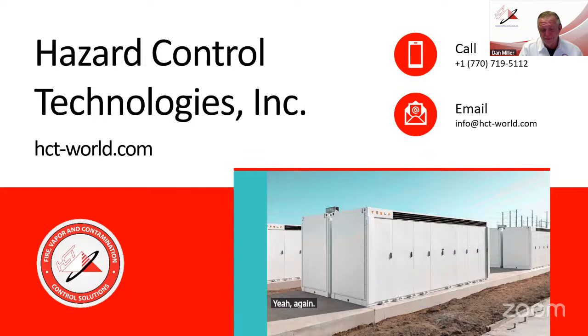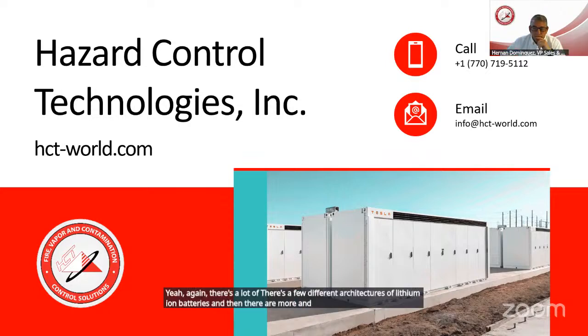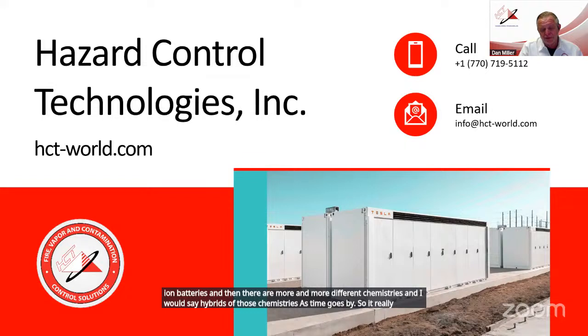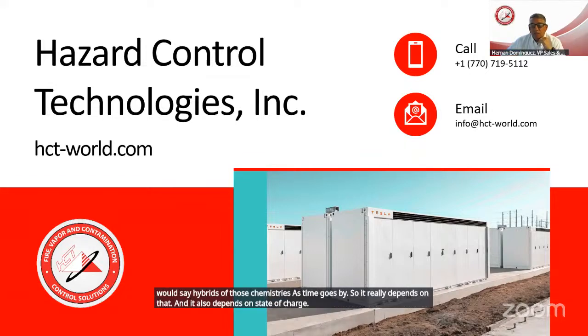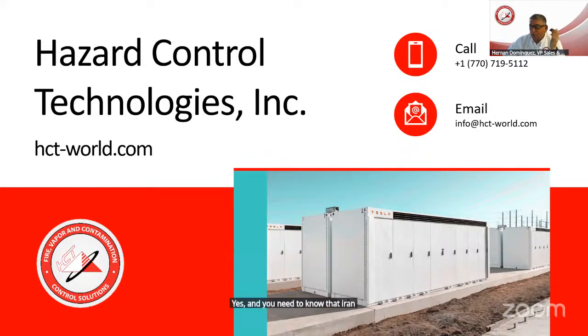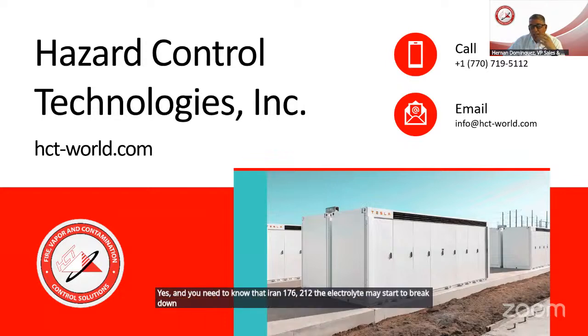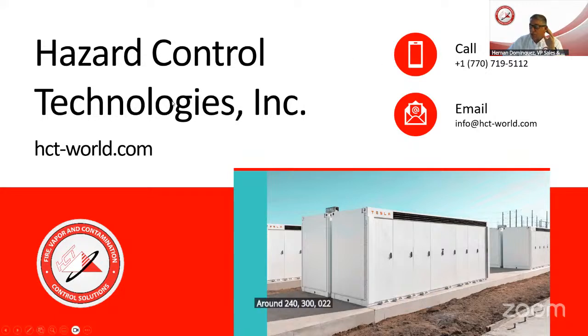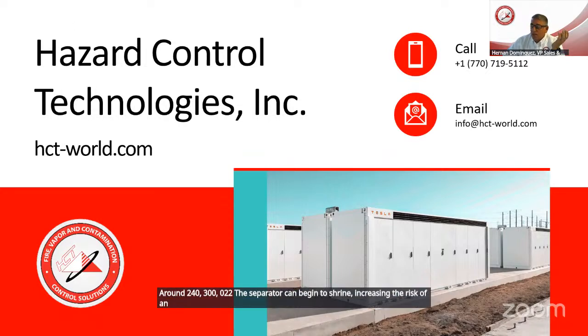There are a few different architectures of lithium-ion batteries, and more and more different chemistries, and hybrids of those chemistries as time goes by. So it really depends on that, and also on state of charge. Around 176 to 212 degrees, the electrolyte may start to break down, leading to gas generation. Around 240 to 302, the separator can begin to shrink, increasing the risk of internal short circuits. As temperature continues rising to 392 to 482, thermal decomposition of the cathode material may occur, releasing additional heat and gases. This is why I put that explanation in the chat.